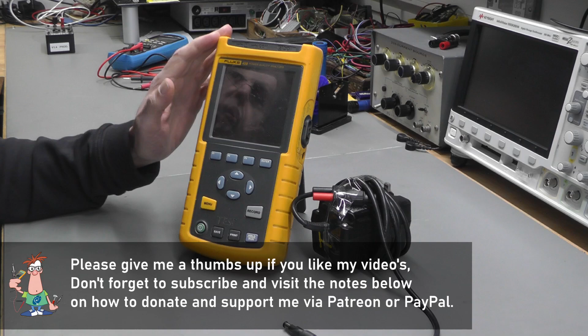The Fluke 43B is a power quality analyzer, all about measuring power. It's battery operated, and you'd take it out onto site or inside equipment to measure voltage, current or frequency problems on the power side, single phase and three phase, looking at harmonics, sags and swells in voltage, transients, inrush currents, and it can log data for up to 16 hours.